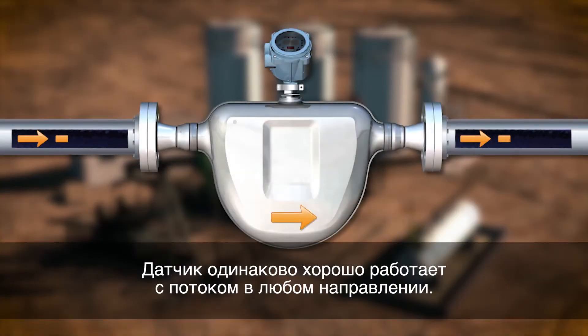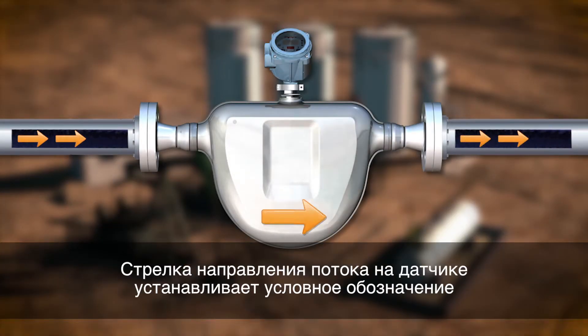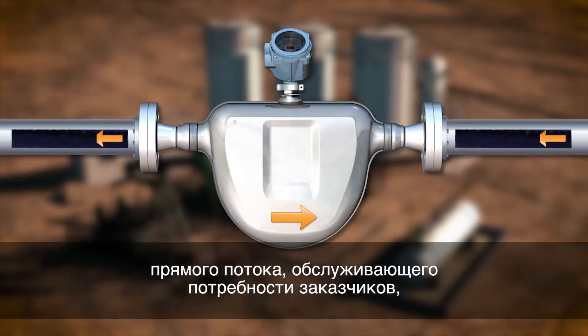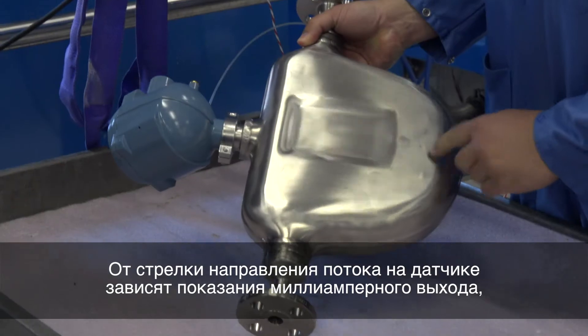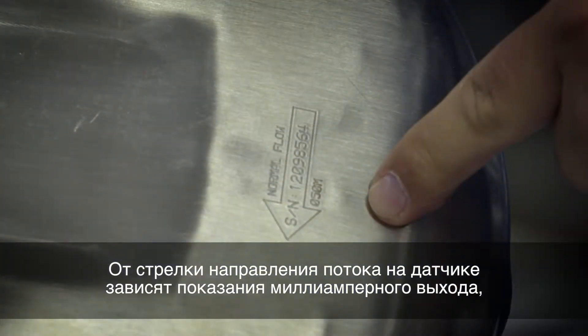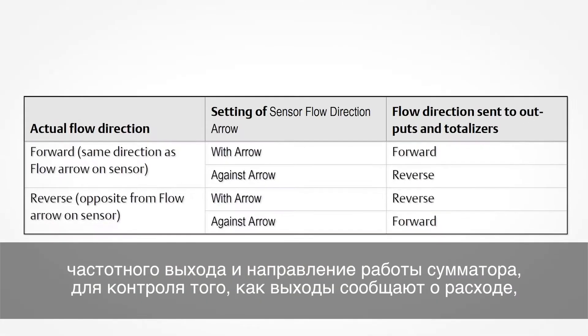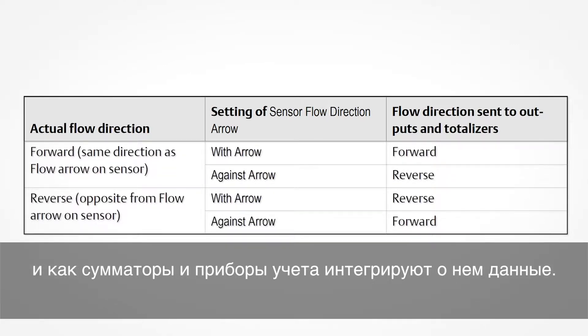The sensor works equally well with flow in either direction. The sensor flow direction arrow establishes a convention of forward flow to accommodate customers who need to define forward and reverse flow for process purposes. The sensor flow direction arrow interacts with milliamp outputs, frequency outputs, and totalizer direction to control how flow is reported by the outputs and accumulated by the totalizers and inventories.